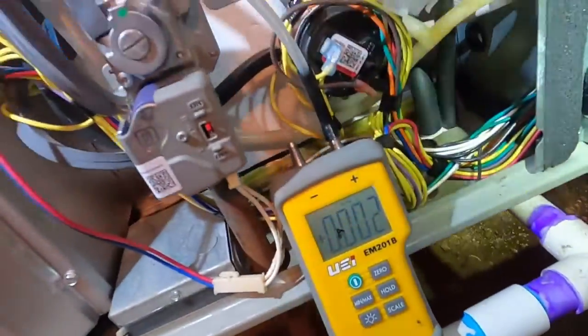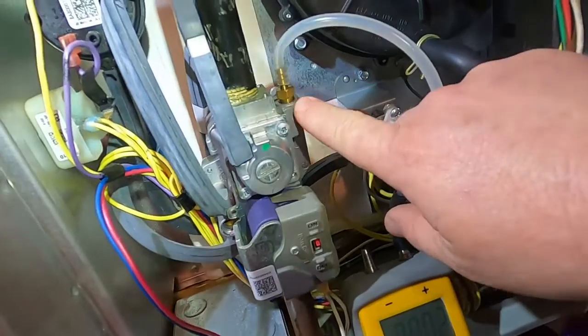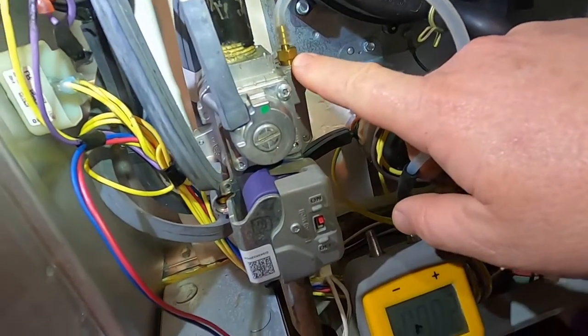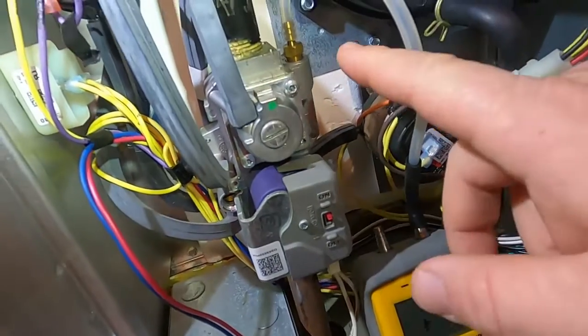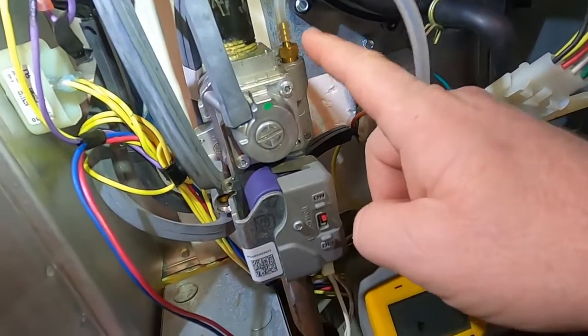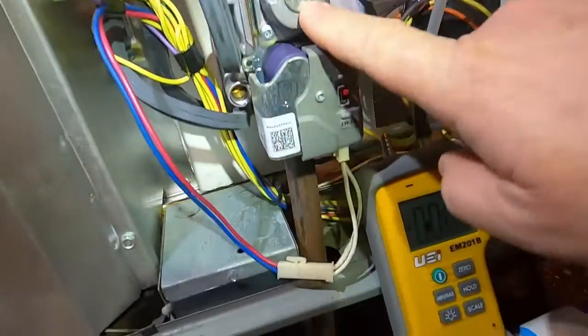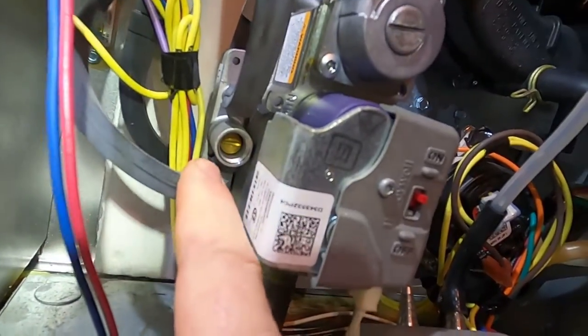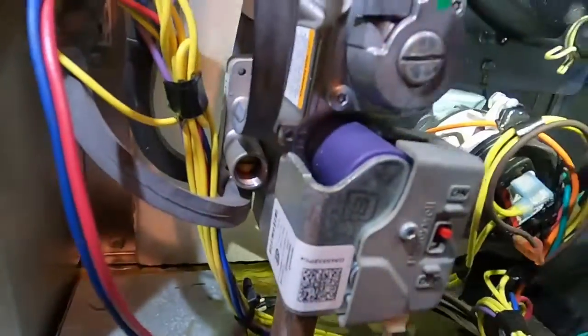Everything is connected. There's only one tap you need to use on this — there are no separate taps for first stage or high stage. Your adjustment for the high is right there, and your adjustment for the low is right back here — and it's missing the cap.